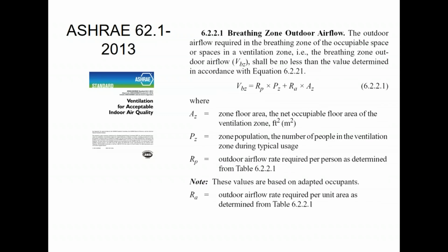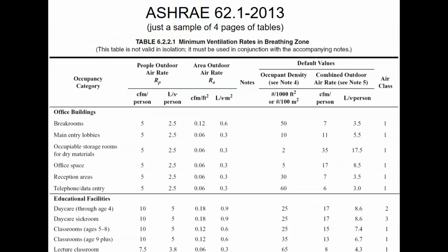How much ventilation air do you have to bring in? Here's the formula for that. The formula makes it sound scary, so I'm going to skip the formula and show you the table, which makes it look slightly less scary. In this case of an office building that I have highlighted, I need 5 CFM per person plus 0.06 CFM per square foot. ASHRAE 62 and IMC both do it this way, a per person and a per square foot number, and you add them together. They've been doing it that way for over 10 years.